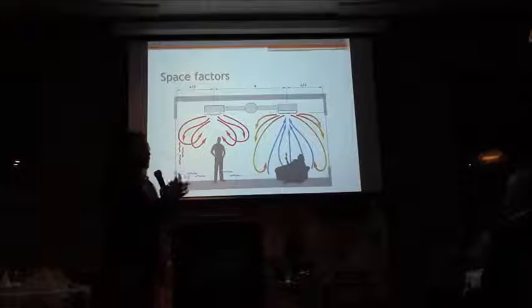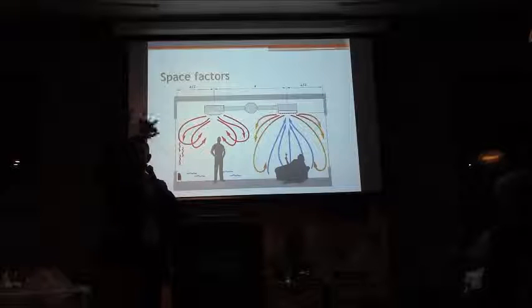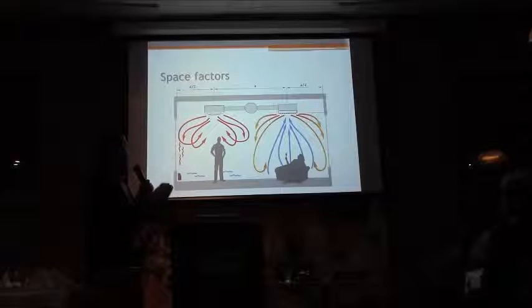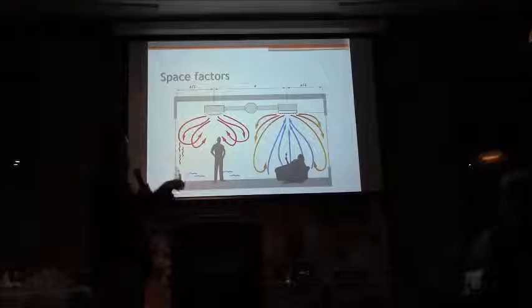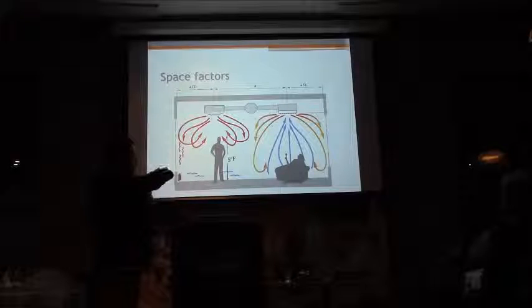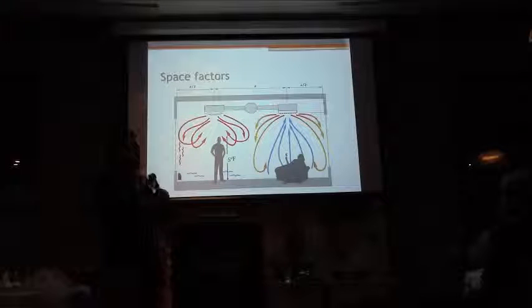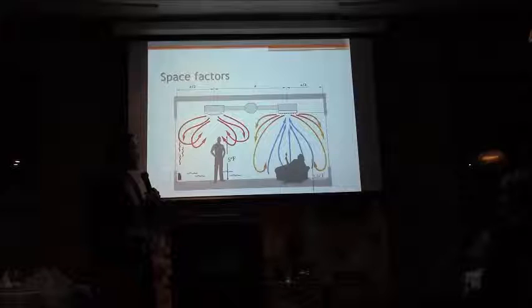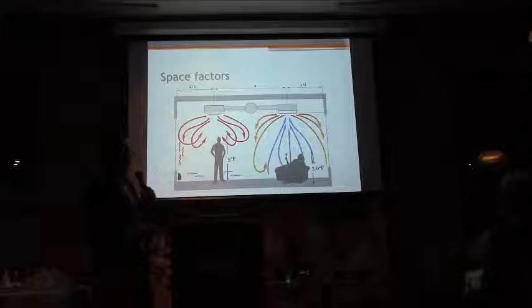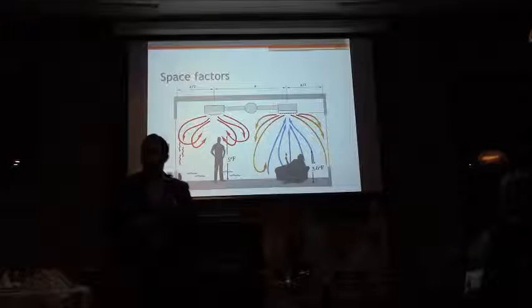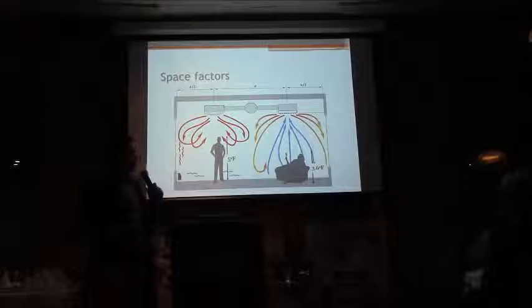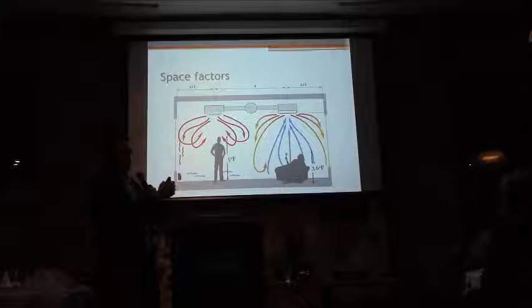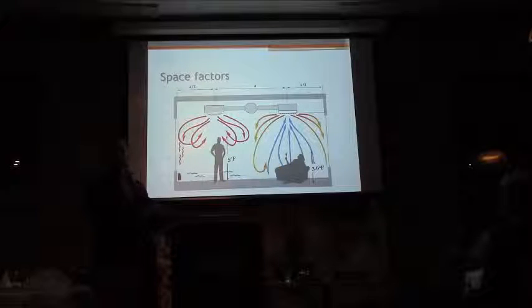First of all, it's a waste of energy. You have all that hot air that's just sticking to the ceiling. And second of all, you want to have a maximum temperature gradient vertically of 5 degrees Fahrenheit if you're standing. And if you're sitting down, that's 3.6 degrees Fahrenheit. So those are a lot of factors to keep track of as an HVAC designer.